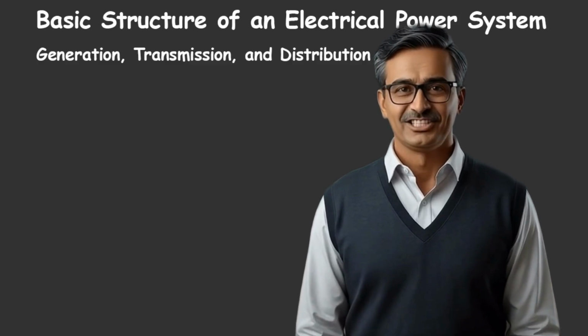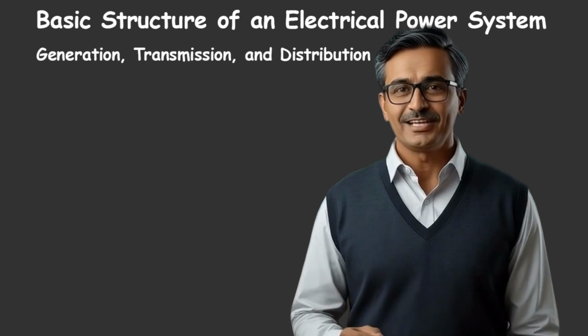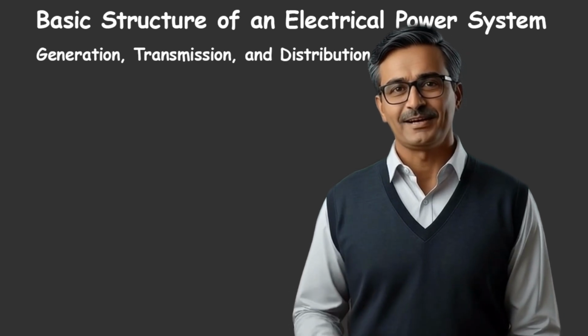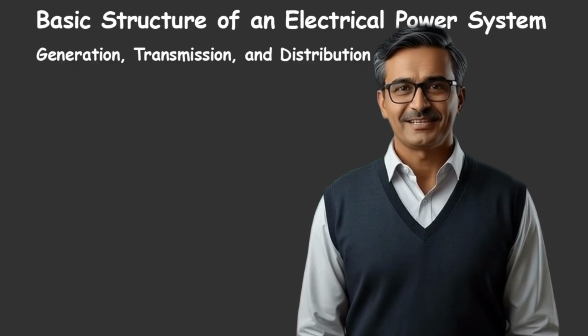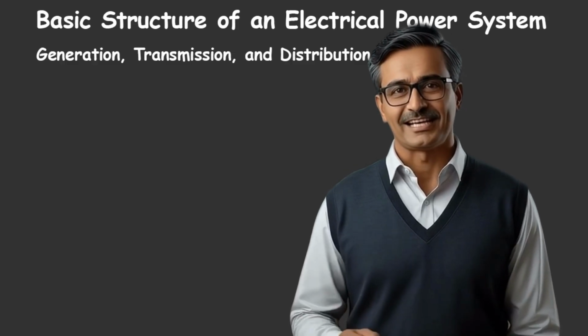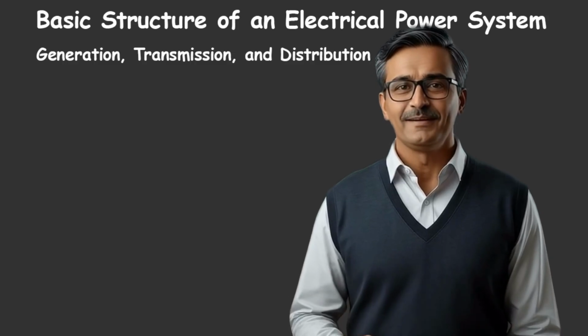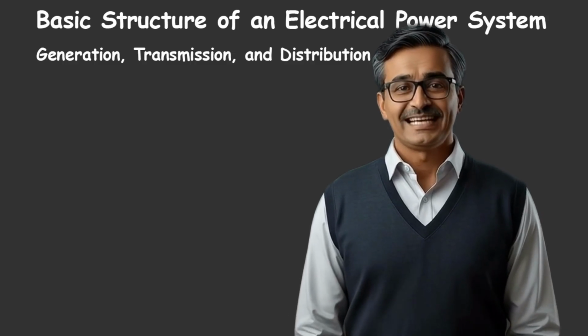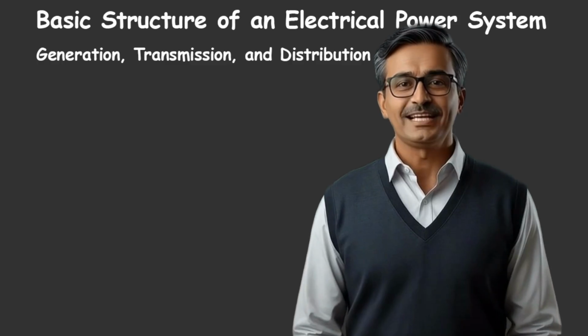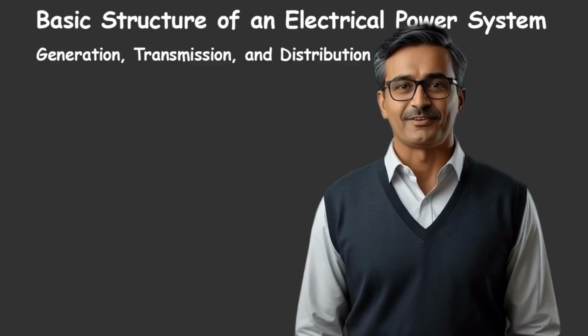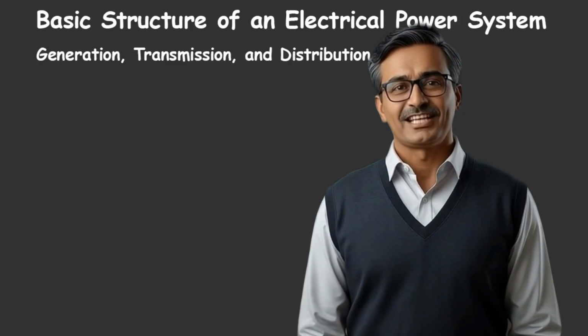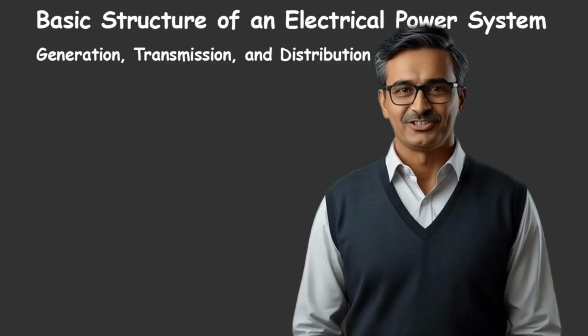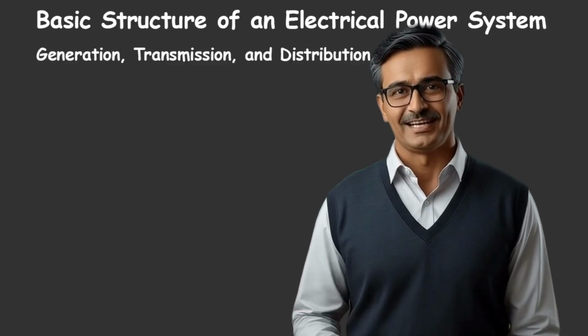The generating station generates power at a low voltage level, typically about 11 to 25 kilovolts. This is because generation at a low voltage level is more economical than generation at a high voltage level. Although we are not going to discuss in detail the reasons for low voltage generation, you can keep in mind for the time being that low voltage generation reduces the insulation requirement of the alternator or generator.